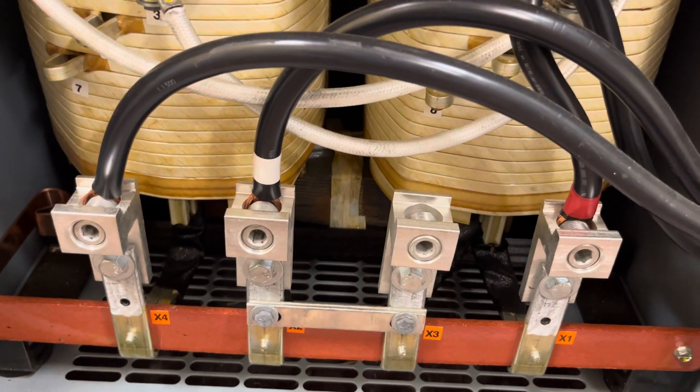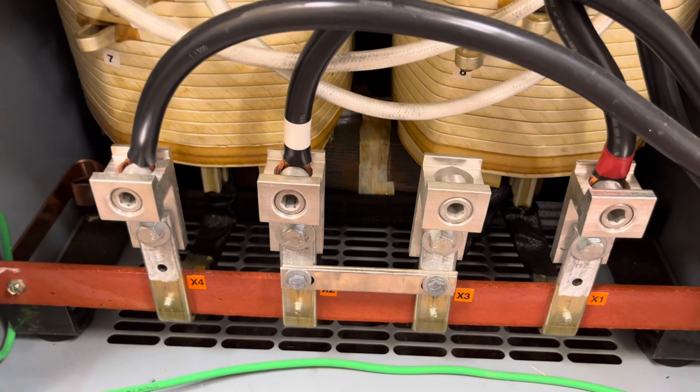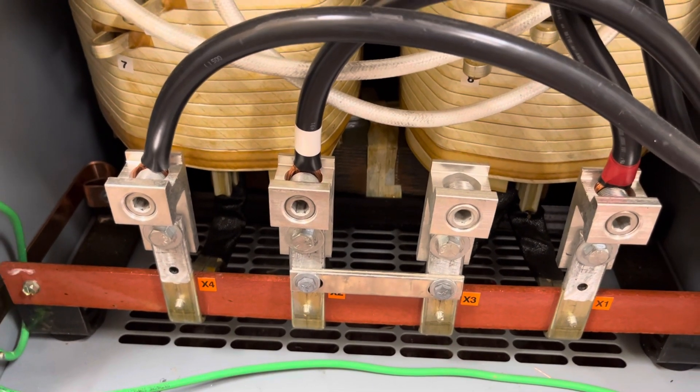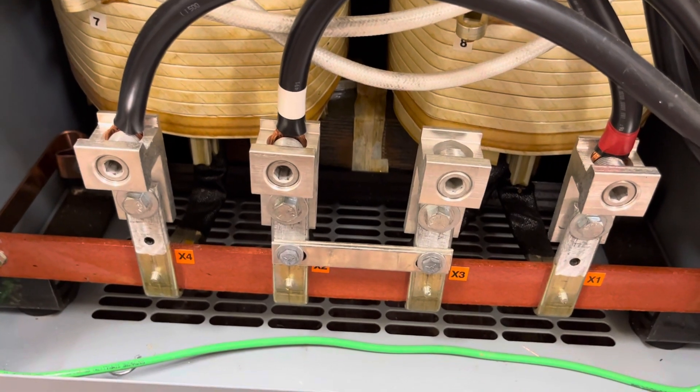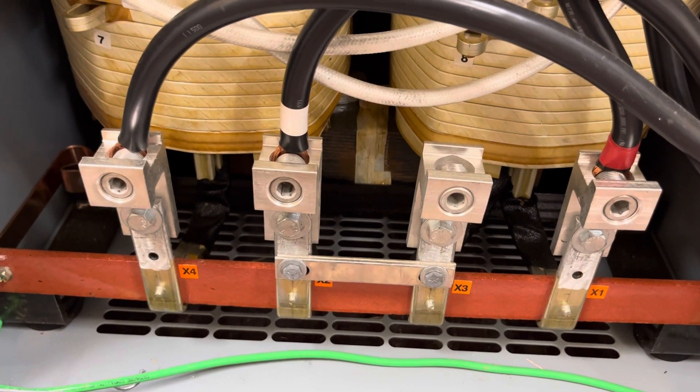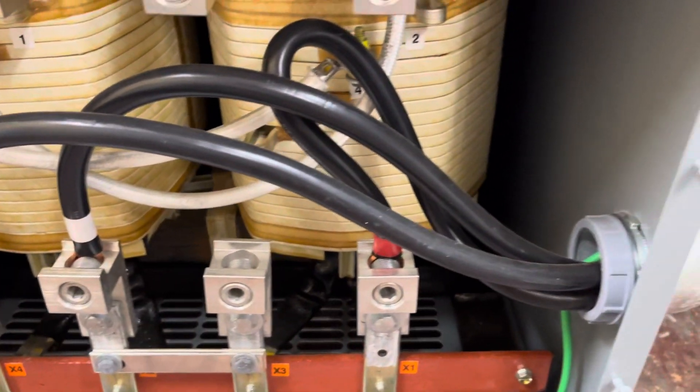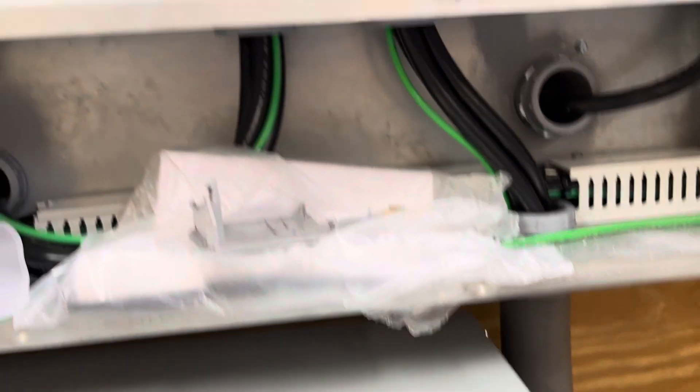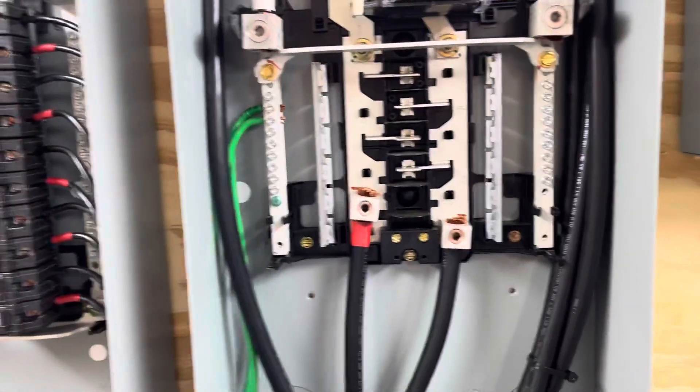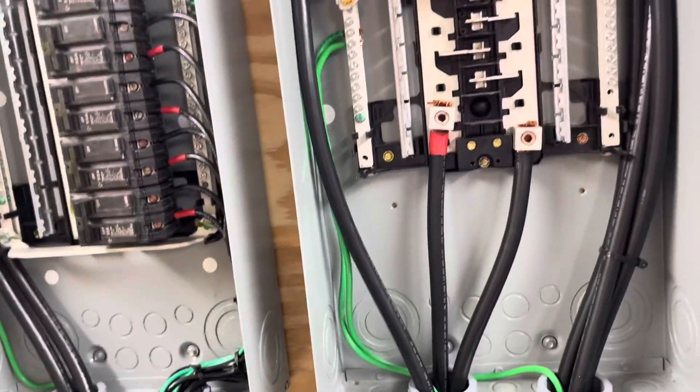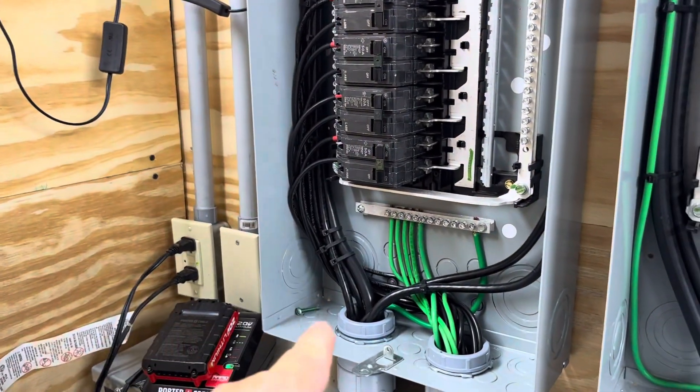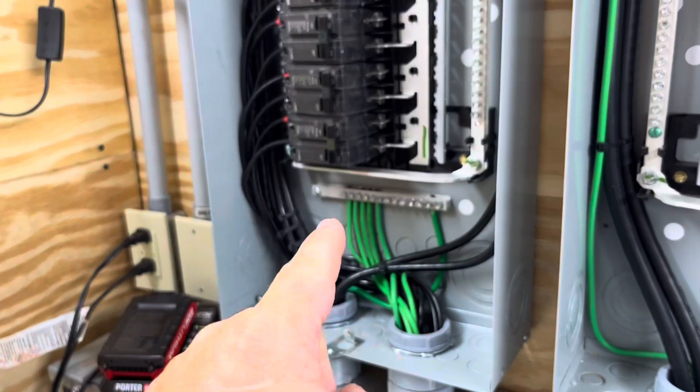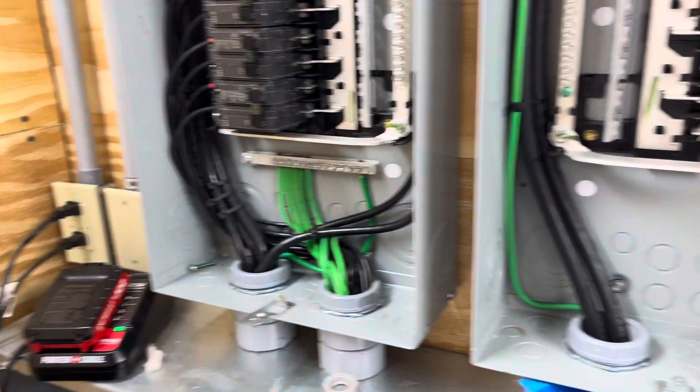Now, this neutral has to be bonded. I didn't bond it in this transformer because I wanted to have control over that. You could bond it in the transformer here if you wanted to, but I've chosen to bond it in what I'm calling my system output panel. So the ground runs from the outside panel, from the ground rod to the outside panel, from there, to this ground bar.